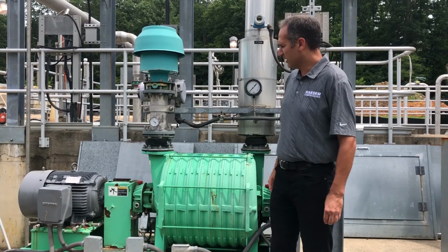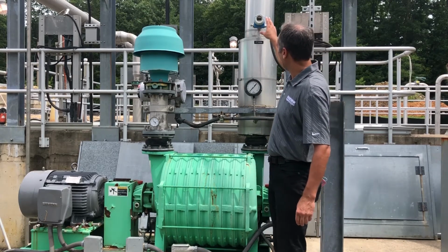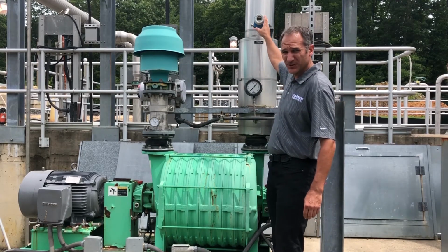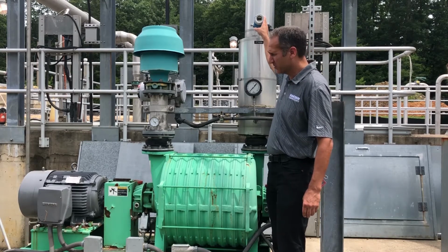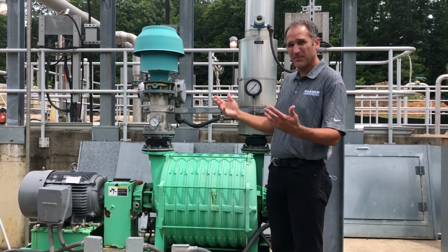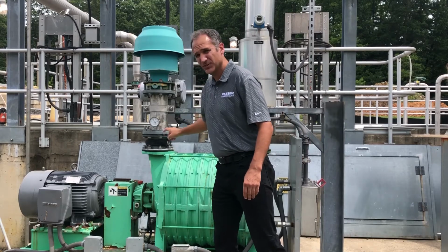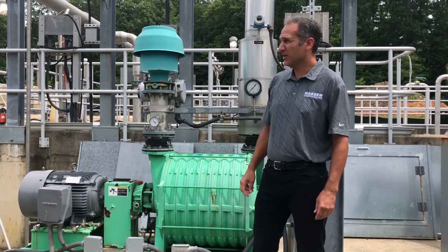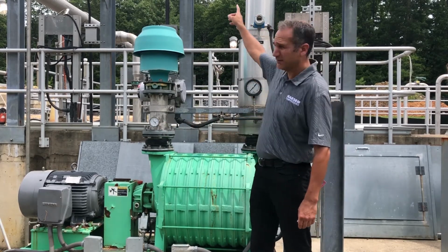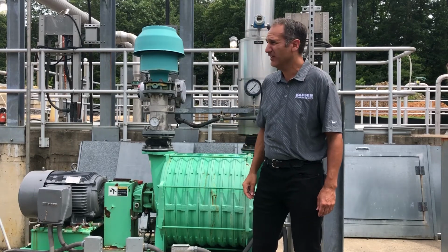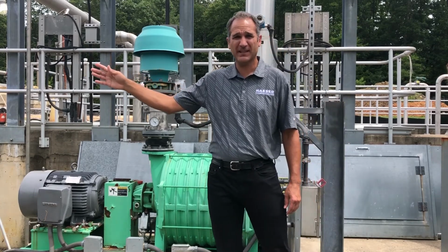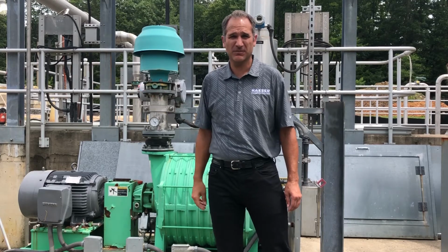So with an audit, we would come in here and measure our outlet pressure. This is the pressure transducer here, so we might grab a signal from there or put another transducer in. We're going to measure ambient temperature, suction pressure, and most importantly, flow rate, which requires finding a place in the pipe to put a flow meter, as well as incoming power back where the power is supplied to the machine.